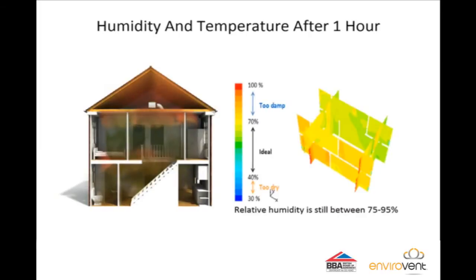Looking at the scale, the CFD model shows that after only one hour the humidity within the dwelling is showing yellow, which means the humidity has fallen to around 80%. After two hours the air has already fallen below 70% and the heat at high level has been totally redistributed around the property, saving energy.